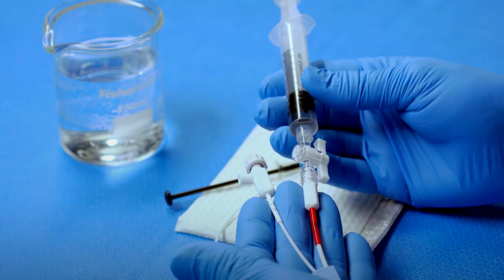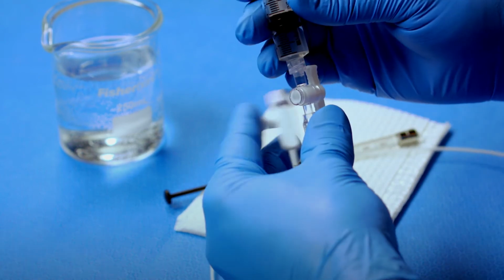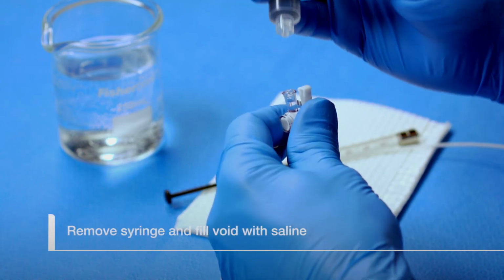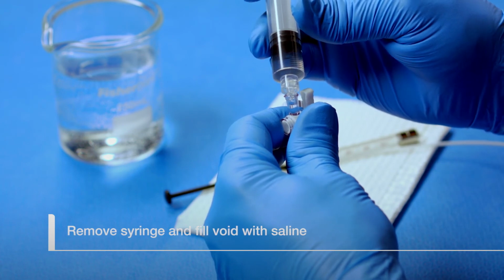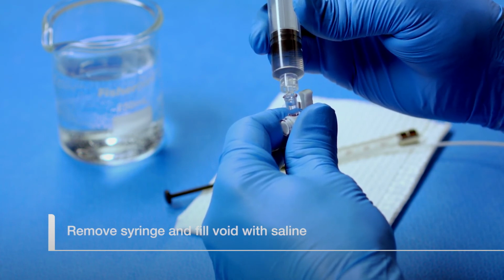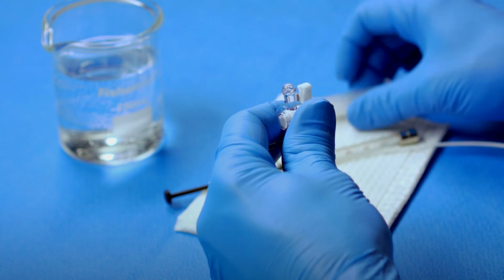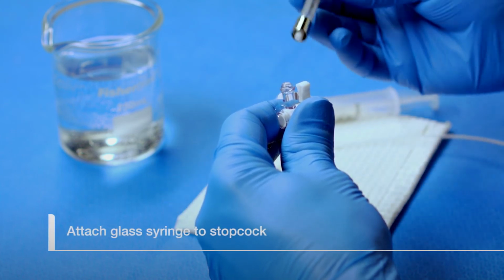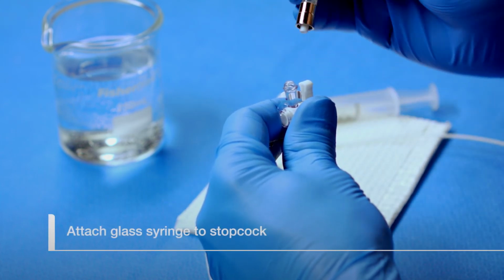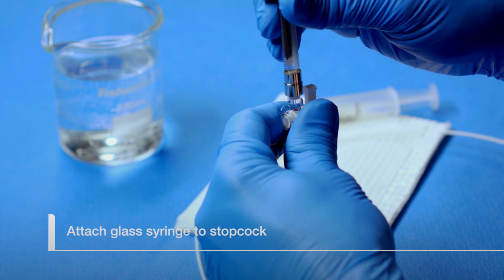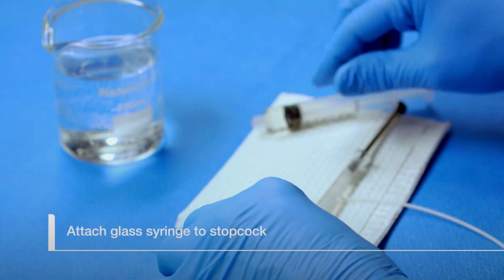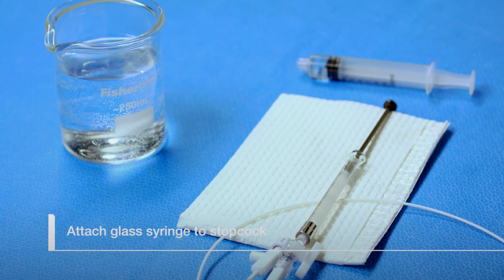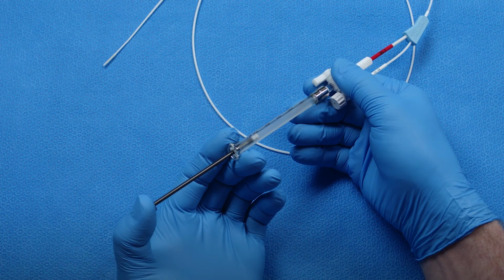While holding the B5-2C balloon in one hand, remove the 10 cc syringe, using it to fill the void space in the stopcock with saline until it is full, taking care to ensure no large bubbles are trapped in the stopcock connector. Attach the prepared glass syringe to the stopcock port, taking care not to over-tighten the syringe, as it is possible to damage the luer lock fittings.